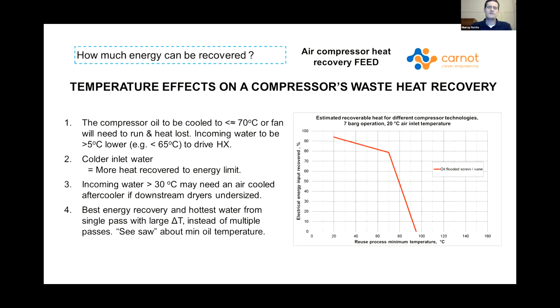So what are the temperature effects from recovering heat from an air compressor? Well, you need to maintain the temperature going back into your air end at that 70 degree sort of mark. I'll just bring up a little spotlight. Can you all see that? So around about this point, you've got to maintain that temperature. This is a heat you can recover from an oil-flooded compressor. It's a mixture of your oil cooler and your after cooler. Hence the reason why you've got your knee there. You're losing that heat from your oil, and then this is a remainder of heat from your after cooler. You're losing some after cooler heat to get to that point as well.